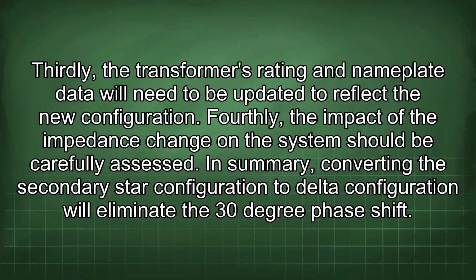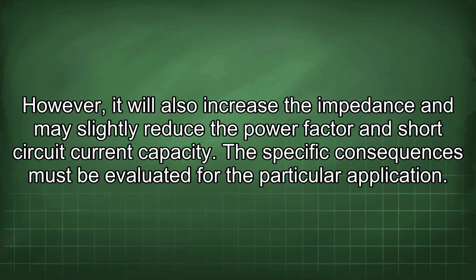In summary, converting the secondary star configuration to delta configuration will eliminate the 30-degree phase shift. However, it will also increase the impedance and may slightly reduce the power factor and short-circuit current capacity. The specific consequences must be evaluated for the particular application.